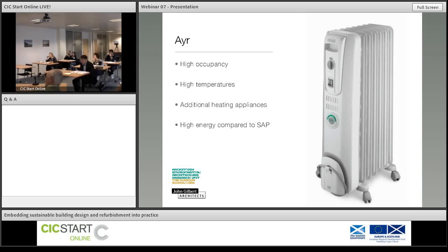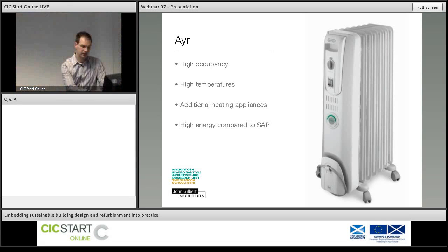And people in the other houses have perhaps not been able to refine that to that level. And I think it has to be said that throughout, the use of trickle ventilation was poorly understood, and even to that house that said they couldn't reach the trickle ventilation. So I think background ventilation is an issue.